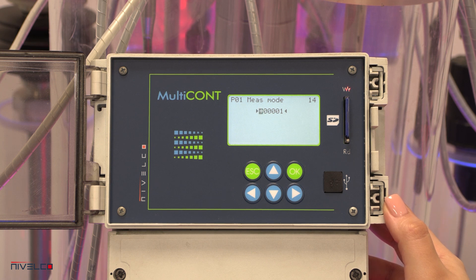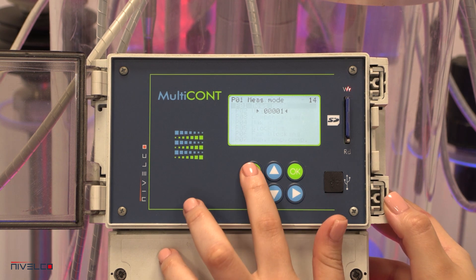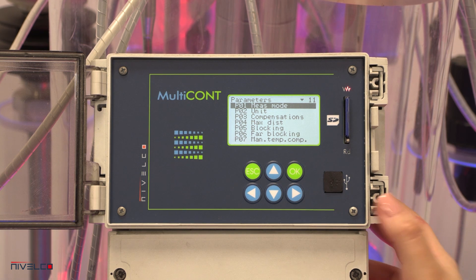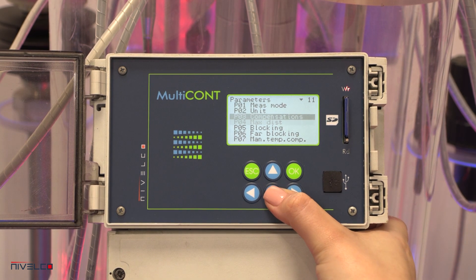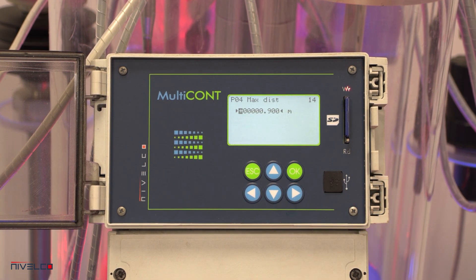Level transmitters measure distance, and all other values are calculated from that, considering the properties of the container and the medium. The maximum distance can be changed. We use a small plexiglass tube for testing, so we set the value to 0.9 meters.